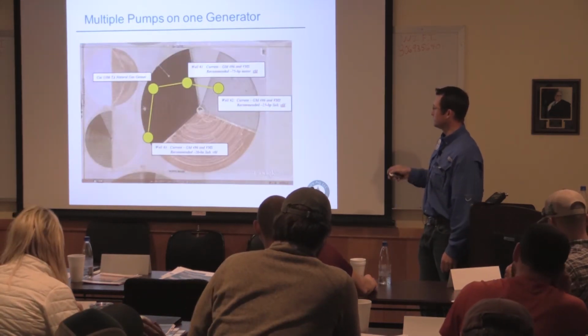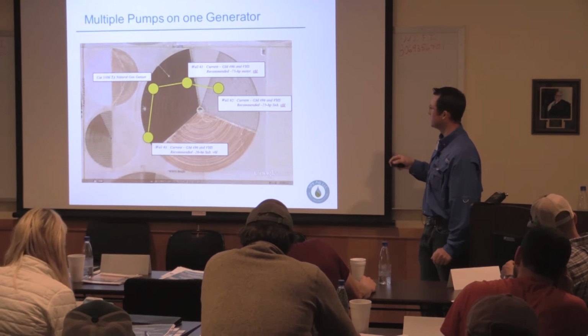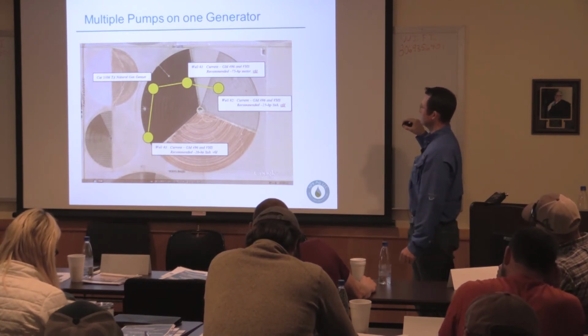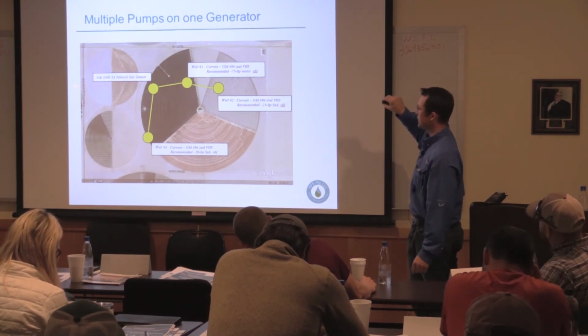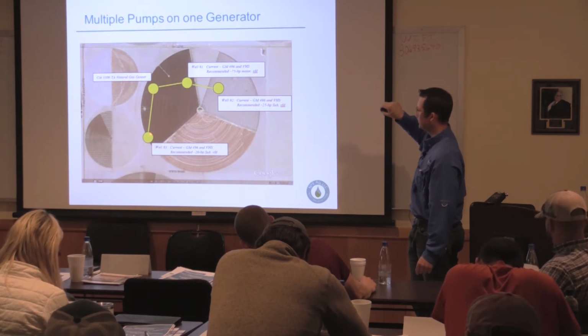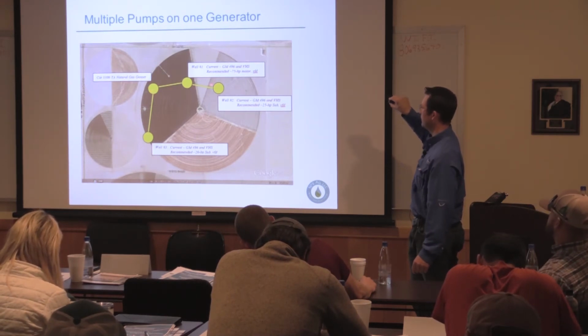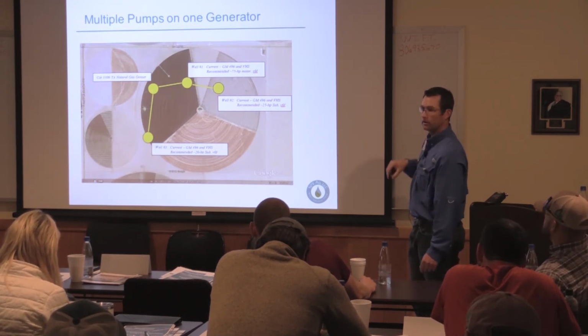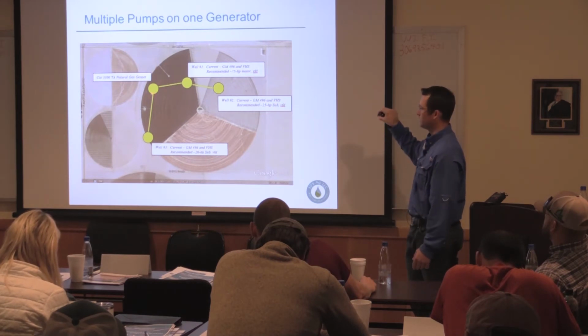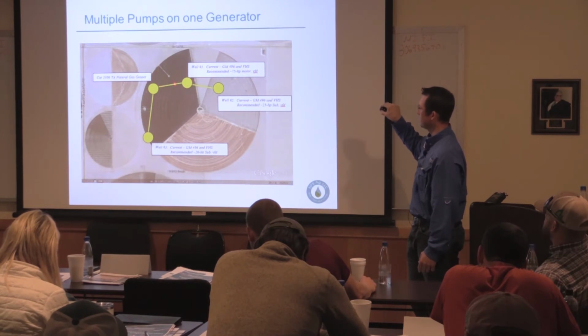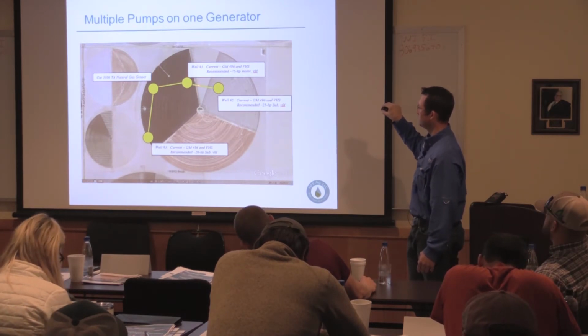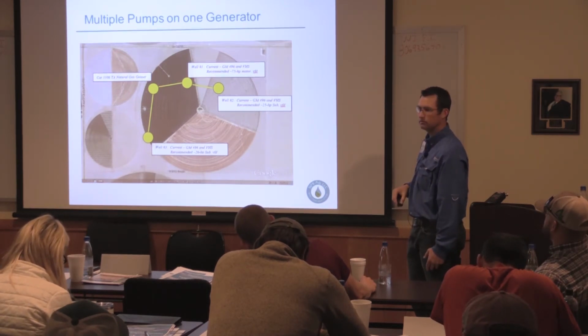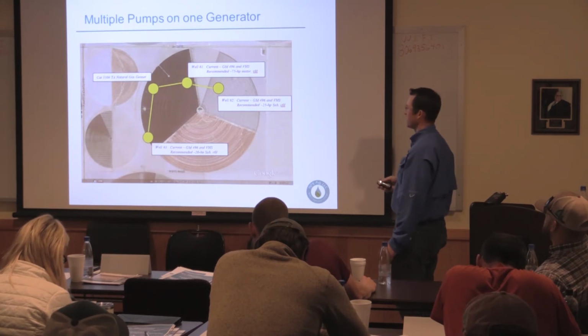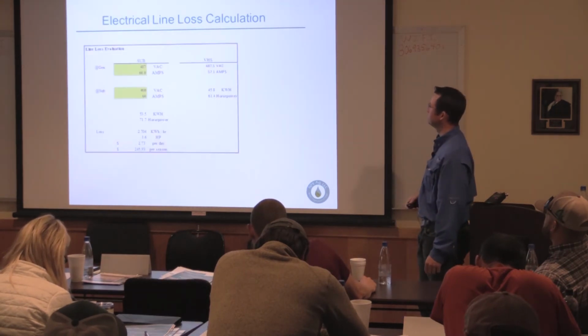So this would be a typical system. This was the system actually that I had tested. This is the location of the genset. It's got a run going this way, and then a run and a run going this way. Okay, so you have to be mindful of that. This wire size just has to be enough to accommodate this. This wire size has to take care of this well and this well. This wire size only has to take care of this well. Okay, so that's kind of the map you're going to look at for your loading.